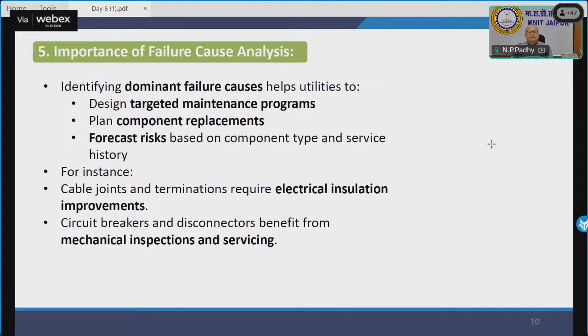So let us discuss a comprehensive life modeling framework to evaluate the reliability of electrical components in a distribution system under the influence of electrical, mechanical and thermal stresses. The model incorporates empirical aging mechanisms and statistical probability functions, very new models. When I talk about physical aging models, the degradation mechanisms considered include partial discharge, water treeing, electrochemical breakdown, thermal aging and mechanical fatigue. The aging follows two principal empirical models: the inverse power model, IPM, for electrical and mechanical stress, and then the Arrhenius model for thermal stress.